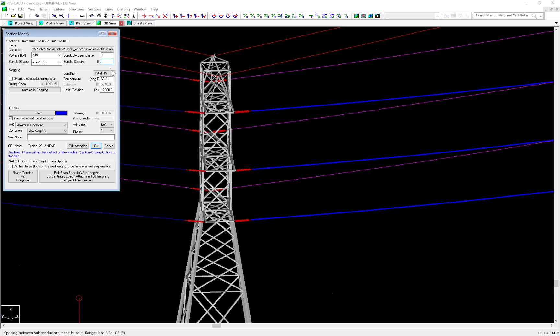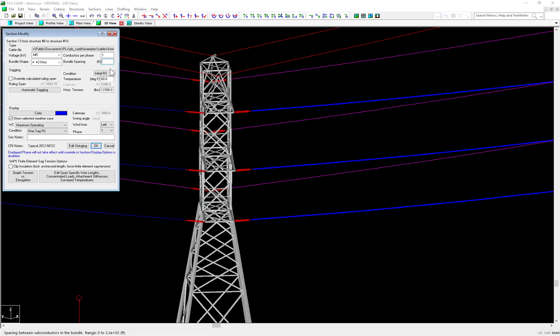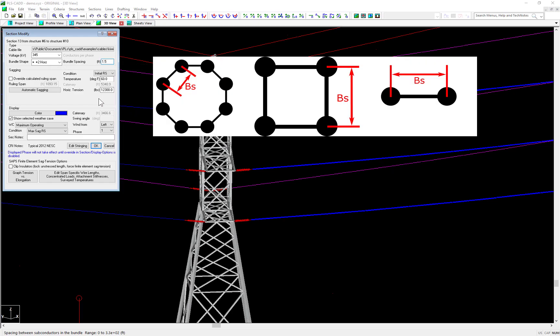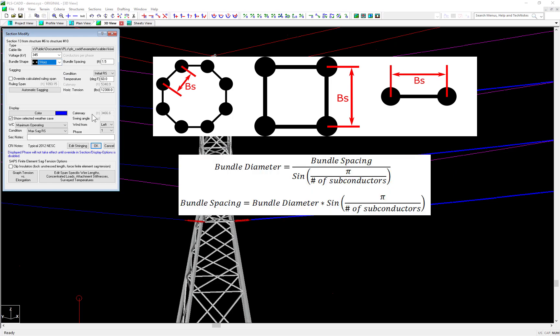First, the spacing is entered in units of feet, not inches. So if you have the popular spacing of 18 inches, be sure to enter 1.5 feet and not 18 feet. Second, the bundle spacing is the minimum separation from one subconductor to another and not the bundle diameter. Unless you pick a two horizontal or two vertical bundle, then it will be the same. Otherwise, if you wish to enter the bundle diameter, the bundle spacing can be solved for using these equations.